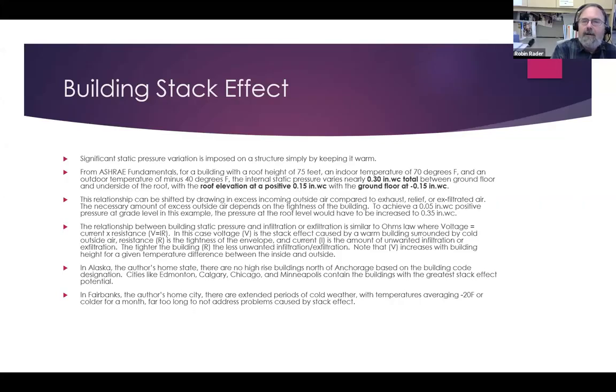So from ASHRAE Fundamentals, you can see that a building with a roof height of 75 feet with an interior temperature of 70 degrees and an outside temperature of minus 40, the internal static pressure varies nearly 3/10 of an inch, with the static pressure at the roof elevation at a positive 0.15 and at the ground floor at a negative 0.15.